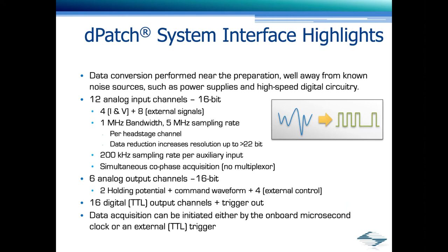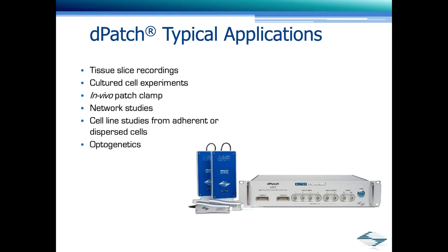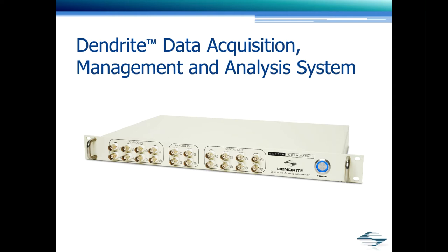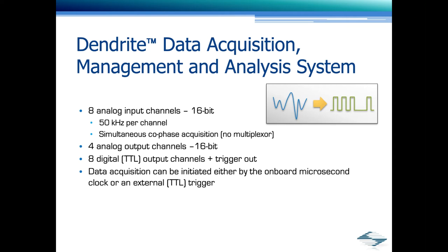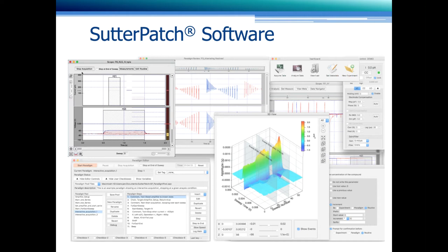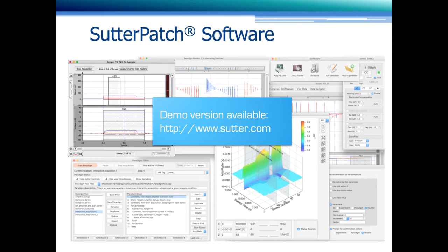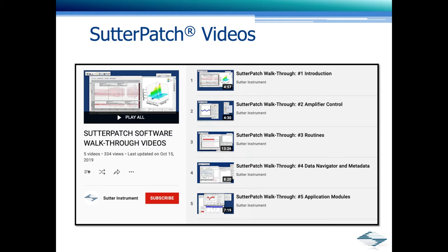Another important highlight is the bandwidth and sampling. Each DPatch head stage is capable of one megahertz bandwidth at five megahertz sampling rate. So the DPatch can do everything that the IPA can do, but it's very well suited for single channel recordings, recordings from nanopores, dynamic clamp experiments, and any application that requires high bandwidth. If you already have an amplifier available, then the Dendrite is your connection to Sutterpatch. The Dendrite is a standalone data acquisition interface that shares the same specifications as the IPA in terms of the interface section. Sutterpatch software is what drives all of our amplifier systems and the Dendrite. I'm not going to go into all the details of the feature set. You can get a demo version available on our website. We also have tons of walkthrough videos and tutorial videos available on our YouTube channel.